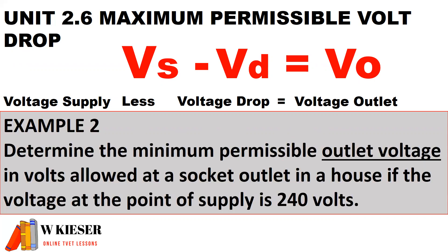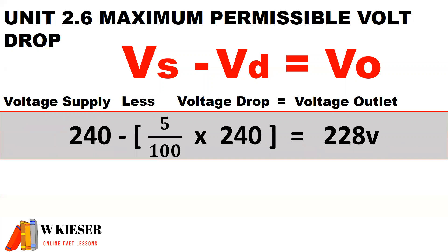To determine the minimum permissible outlet voltage in volts allowed at a socket outlet in a house if the voltage at the point of supply is 240 volts: the minimum outlet voltage is the supply voltage minus the volt drop, therefore 228 volts.